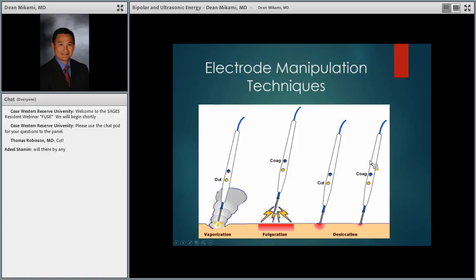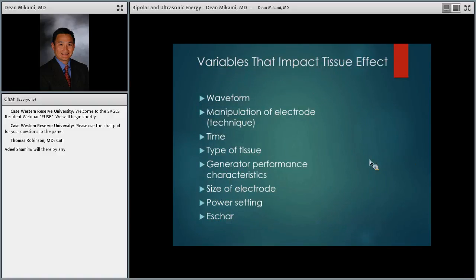So what does this all mean? The variable effects that impact tissue and the effects that you get. We know that waveform is very important: the cut waveform versus the coag waveform, right? With cut, we have a continuous waveform. With coag, we have 94% off, 6% on. Amin talked about manipulating the electrode, right? If you use the edge of the electrode, you're going to have a higher current concentration. You're going to have more current in a very small area, giving you a much higher tissue effect. The time that you hold the pencil or the button down affects what you see at the tissue level. And of course, the generators that you use.